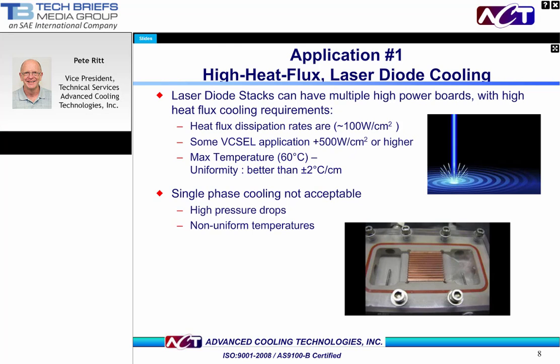Laser diodes typically require lots of power, most of which results in waste heat. Vertical cavity surface-emitting lasers, for example, can have heat fluxes in excess of 500 watts per centimeter squared. Further, the heat loads must be dissipated while maintaining a uniform temperature across the evaporator surface. In many cases, pumped liquid systems are not suitable for these applications. It is difficult or impossible to meet the isothermality requirements of a few degrees C, particularly when hundreds of laser diodes are involved.